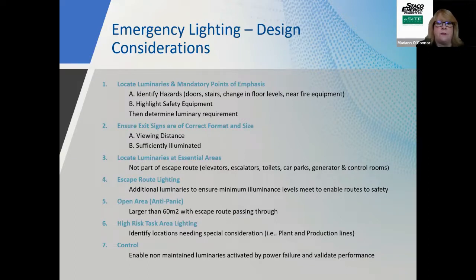Then there's non-essential areas like elevators or escalators or bathrooms. And that has to be taken into consideration. And then you have larger areas where, let's say, you need a little bit more lighting and it's a pass-through on an escape route. And then there's other areas like production lines or a plant floor that you need to look at. Those are kind of high-risk task areas, so you need to say, hey, how much lighting do we need to have here? You want to take a complete look at all of that and see what your power requirements are, and then determine what it is from there, and make sure that you have the backup power to make sure that those lights go on when they're needed in an emergency situation. Next slide.